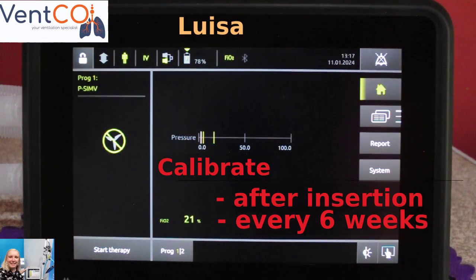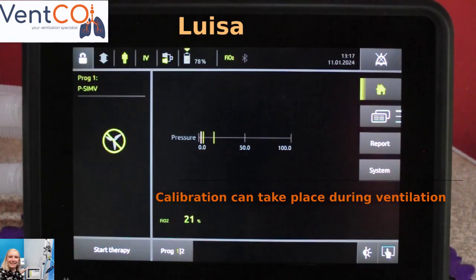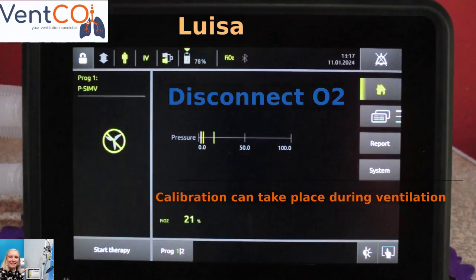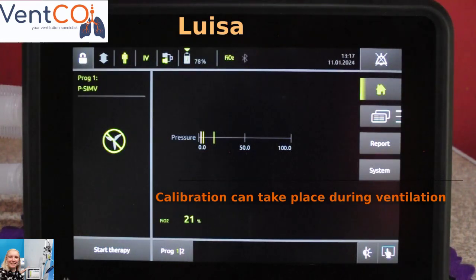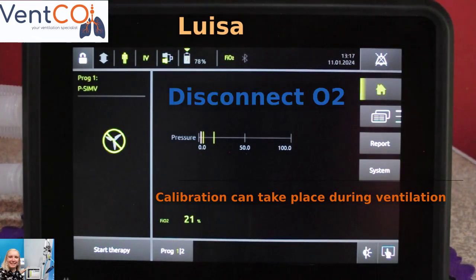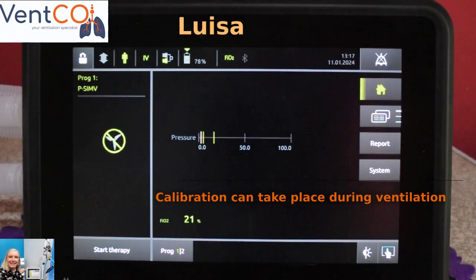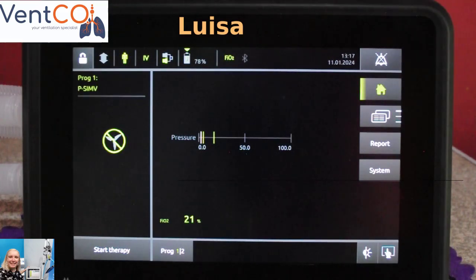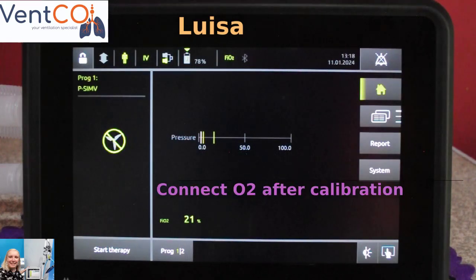The oxygen cell can be calibrated while being connected to a patient, but the oxygen has to be disconnected. So if your machine is connected to a patient and you want to calibrate the oxygen cell, disconnect the oxygen. Please put your patient on some other monitoring device like saturation, and observe your patient for any signs and symptoms of distress, and make sure that you do the calibration and connect the oxygen afterwards.